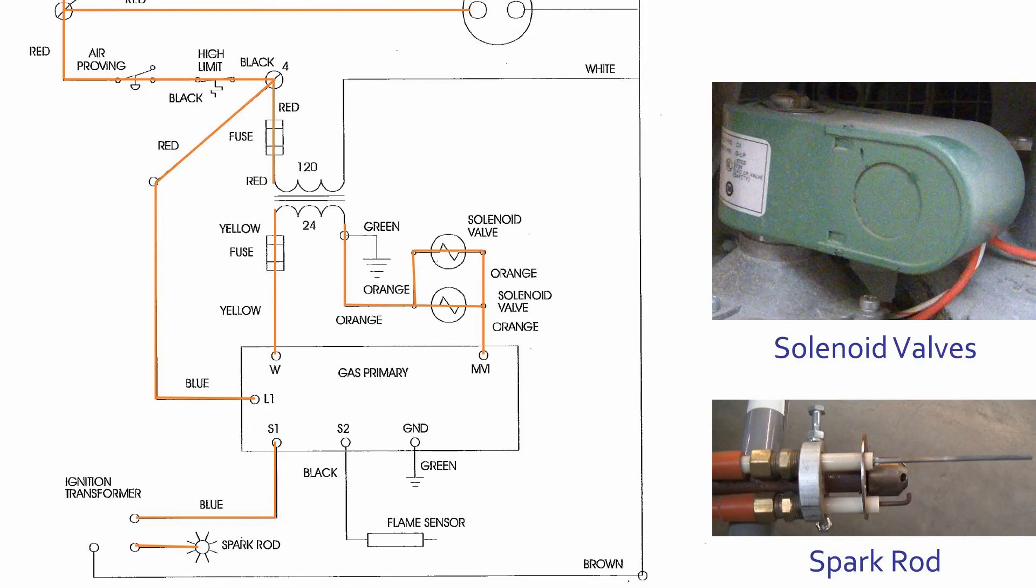The primary gas control opens the two green solenoid valves to allow fuel to the burner. The ignition transformer sends power to the spark rod and the burner is ignited.